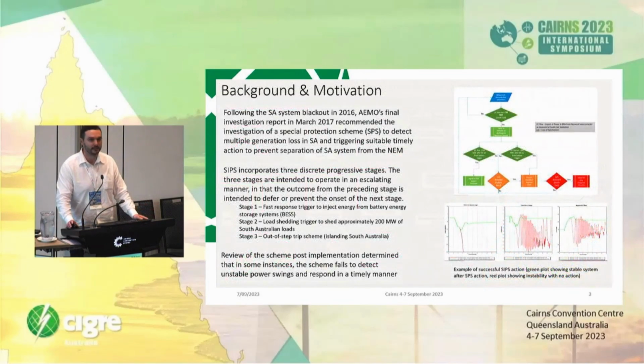So South Australia is prone to severe weather events, ranging from storms to tornadoes, and that's unfortunately what happened on this day in 2016. Tornadoes ripped through the state, and this affected 3 275 kV transmission lines, resulting in 6 voltage dips in a span of about 2 minutes, and this affected the protection and a lot of wind turbines, and a large amount of generation tripped off, about 460 megawatts.